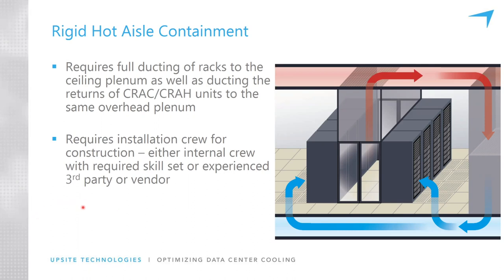Again, this hot aisle containment is where we duct the hot air up to a ceiling plenum, and that creates a ducted path back to the return of the cooling units. This can also be achieved without the chimney. A lot of the benefits of full hot aisle containment can be realized by just ducting the cooling unit to the ceiling plenum and putting return grills in the ceiling, without the chimney. If that's done and airflow is balanced well, then that hot air really doesn't want to go anywhere else besides to this low pressure environment created by the cooling unit. And so you'll get maybe 80% of the benefits of full containment, even without ducting the hot aisle to the ceiling.